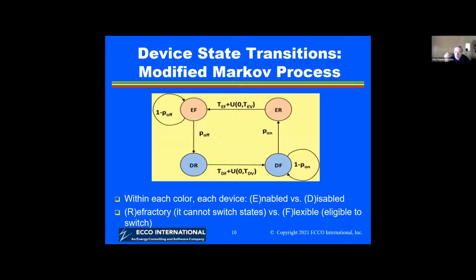The distributed control is based on a modified Markov process. Each device has 4 states: E is for enabled, D is for disabled, R is for refractory - meaning once you move to a disabled state, you're being curtailed, and you stay there for certain milliseconds before you go back, that's the refractory state - and then flexible, where you're eligible to switch.